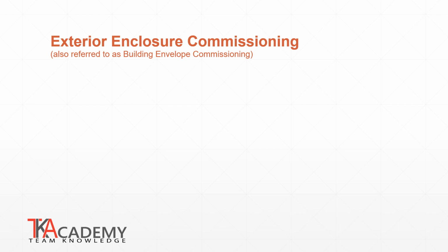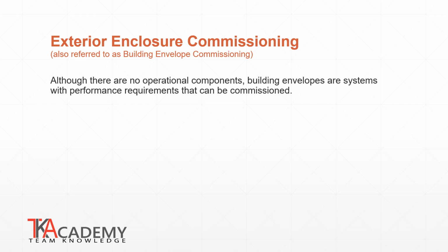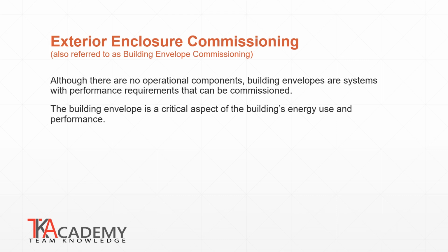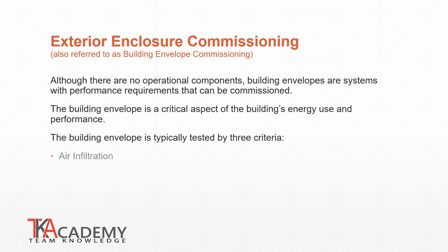Building commissioning is usually associated with mechanical, plumbing, and electrical systems, but any building system can be commissioned. A growing aspect of building commissioning is the commissioning of the exterior enclosure or building envelope. Although building envelopes usually do not have any operating parts, they do have performance requirements that can be commissioned. The building envelope is a critical aspect of the building's energy performance system. The building envelope can be commissioned by performing tests in the three criteria of air infiltration, water intrusion, and transfer of thermal heat energy.